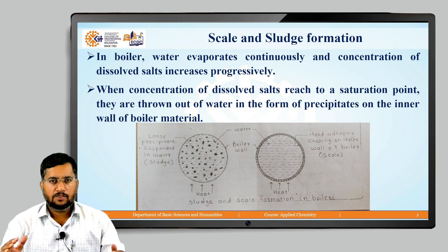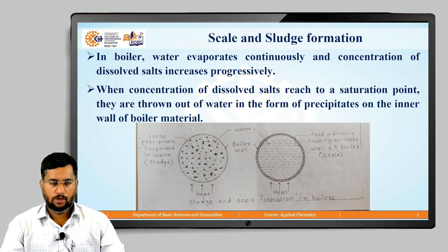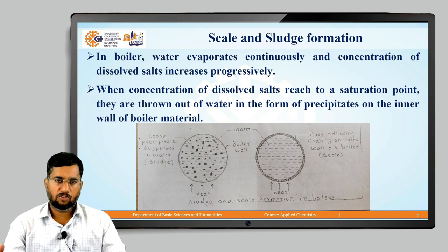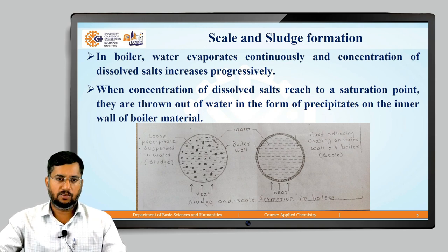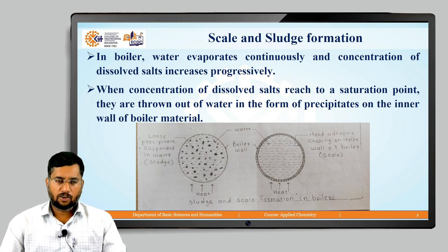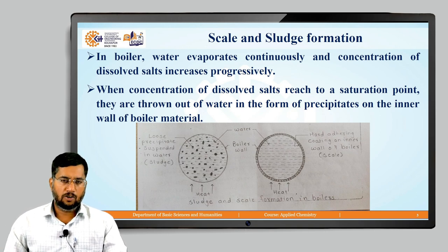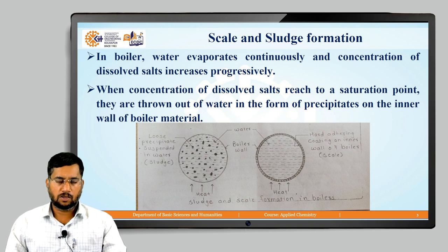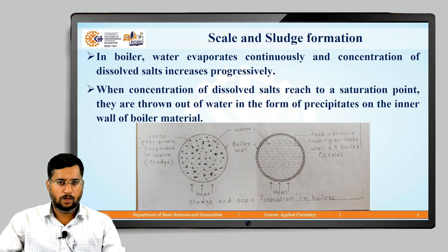Scale and sludge formation is due to dissolved salt impurities. In a boiler, as we provide water to produce steam, water evaporates continuously and the concentration of dissolved salt impurities increases progressively. When that concentration reaches a saturation point, the dissolved salts precipitate out and are deposited onto the inner wall of the boiler.